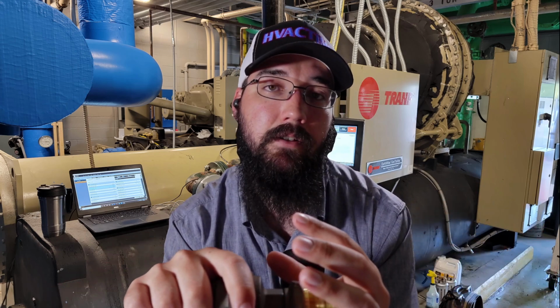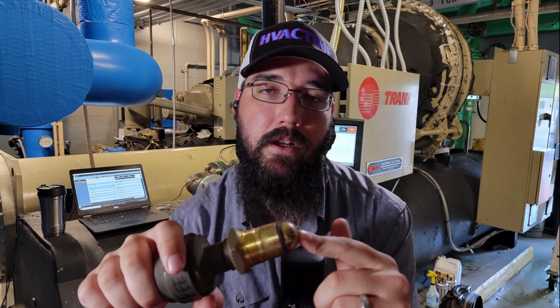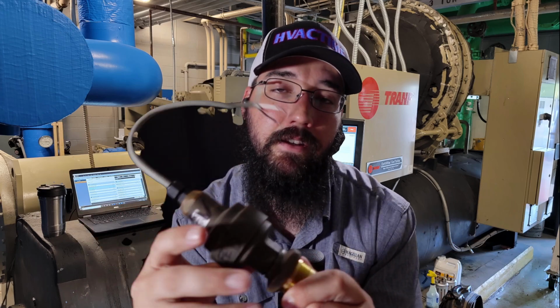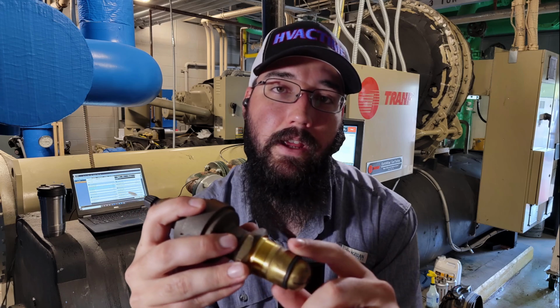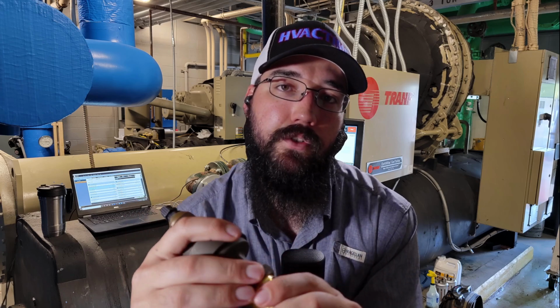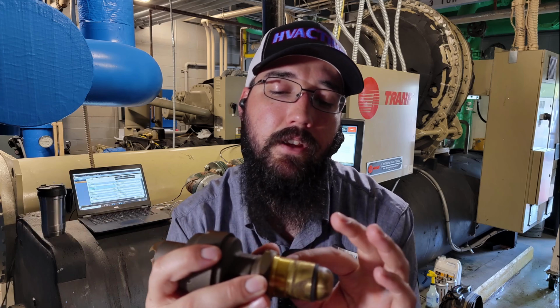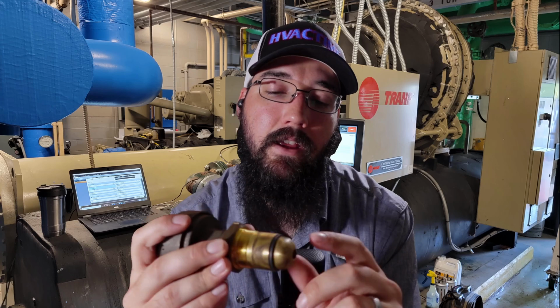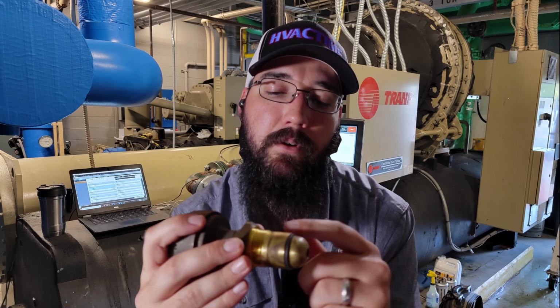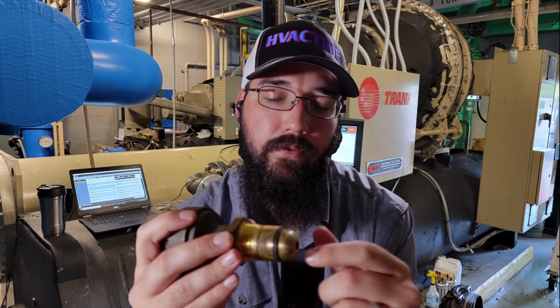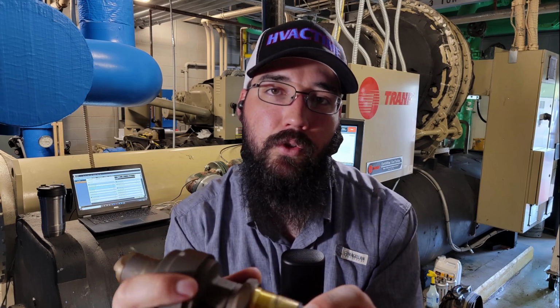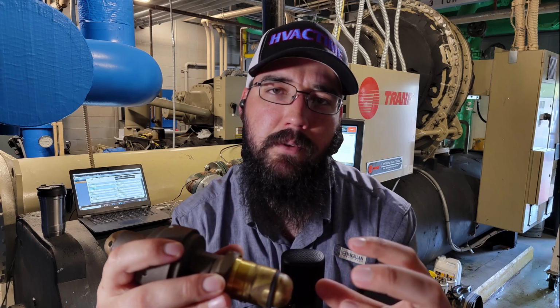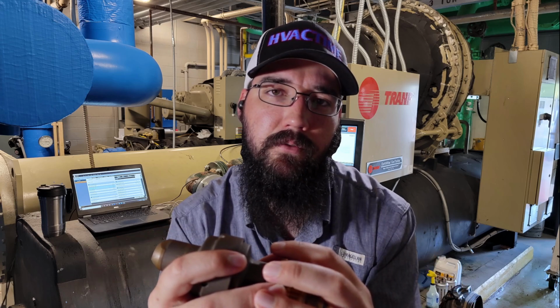The other thing is they'll do that and then forget to draw it back in, and the plunger will be out at an extended position. Then they'll thread that in, and it'll go the majority of the way, and you'll think you're close enough. You just need to finish torquing it down. In reality, you hadn't actually bottomed out yet, and what bottomed out was the plunger to the valve body, not the actual sealing surface. So then you start torquing it down, and you'll end up jamming that Teflon thread assembly and stripping it completely out.